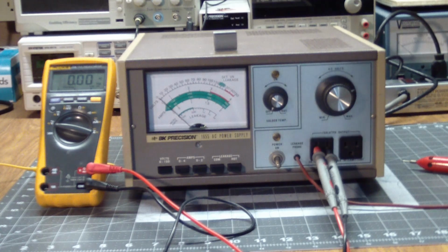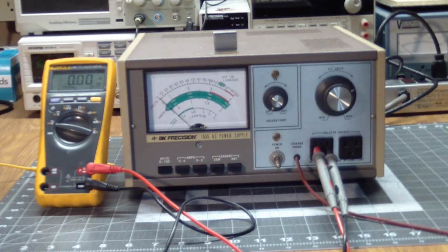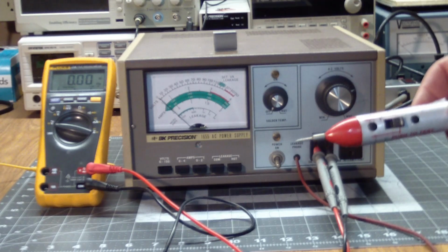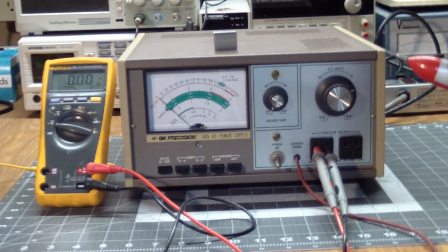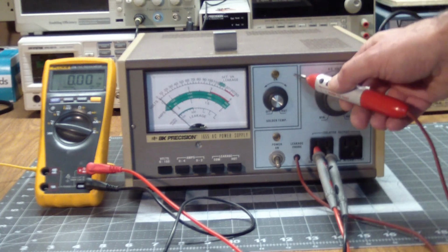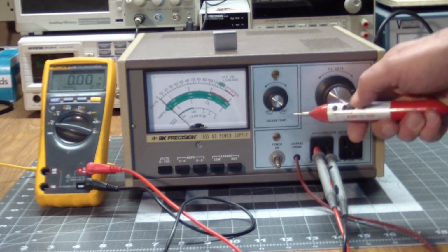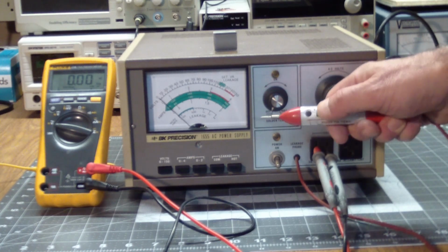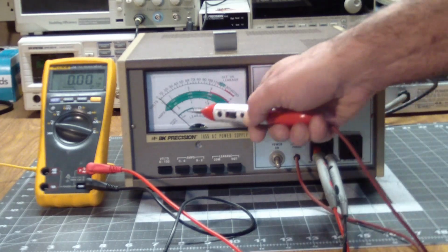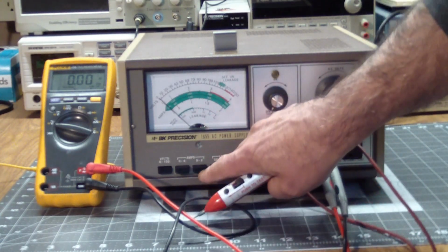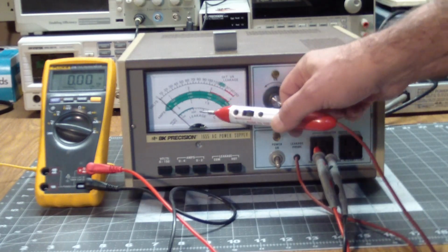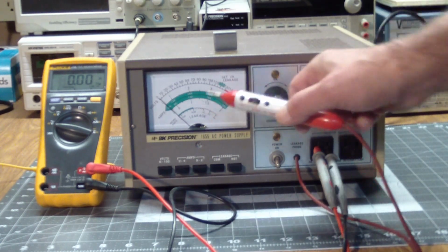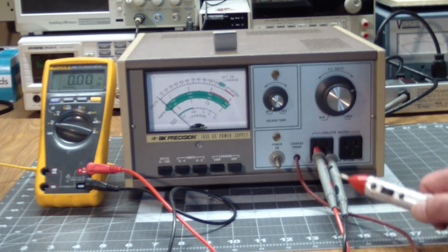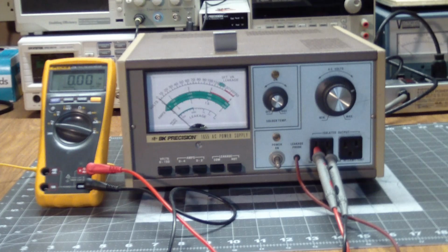Well, she's all buttoned up, and I did some research. Basically, the way you use the leakage probe is you go to the device under test, or whatever it is, you touch a metal part of it, and you have to push here's the button that you got to push forward. And you select leakage, of course. If the leakage current is less than 500 microamps, you're good. And if it's above 500 microamps, watch out, because something is leaking outside.